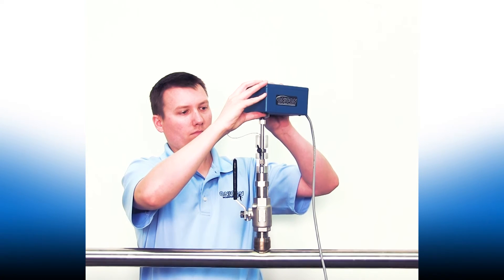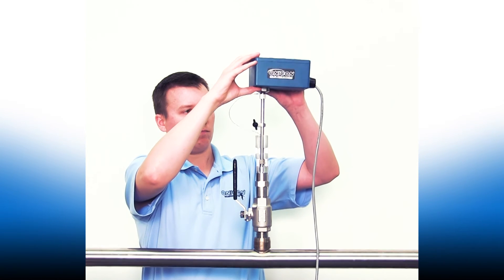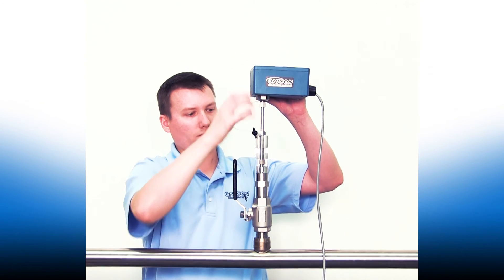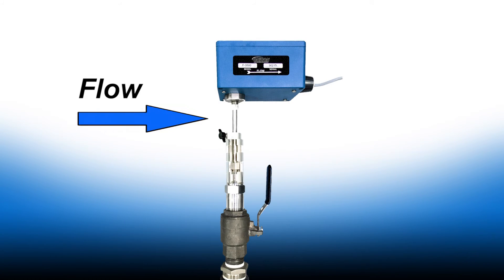Rotate the meter so that the stem is able to slide up and down until the collar sits on top of the alignment tool. Make sure the flow direction on the meter is pointed in the direction of flow in the pipe.